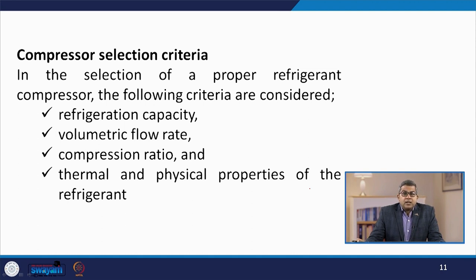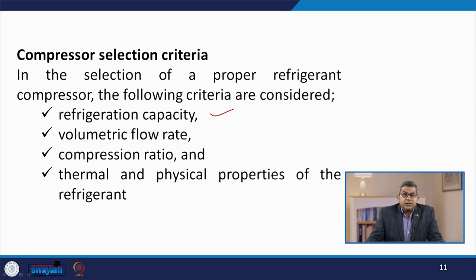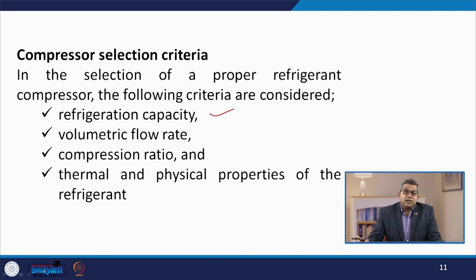Given the variety of compressors available, there must be certain criteria for compressor selection. These include: the required refrigeration capacity, the volumetric flow rate needed — which depends on the refrigeration cycle design and refrigerant used — the compression ratio required, and the thermal and physical properties of the refrigerant, which are essential for assessing compatibility with the compressor.